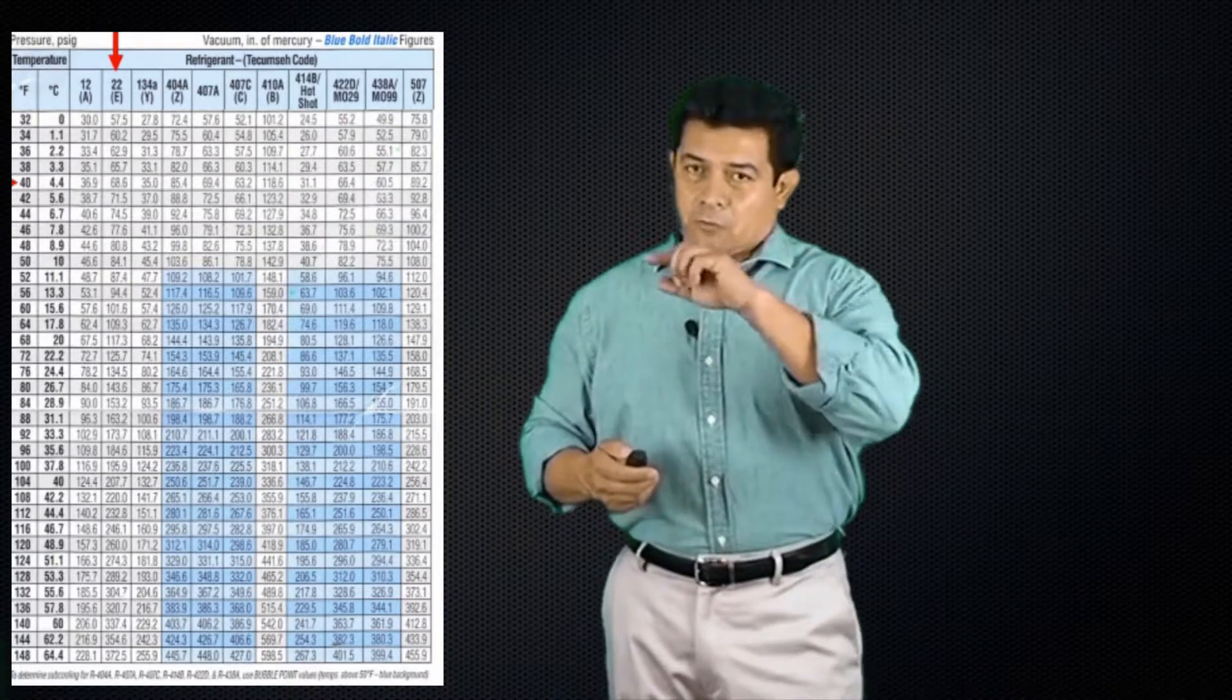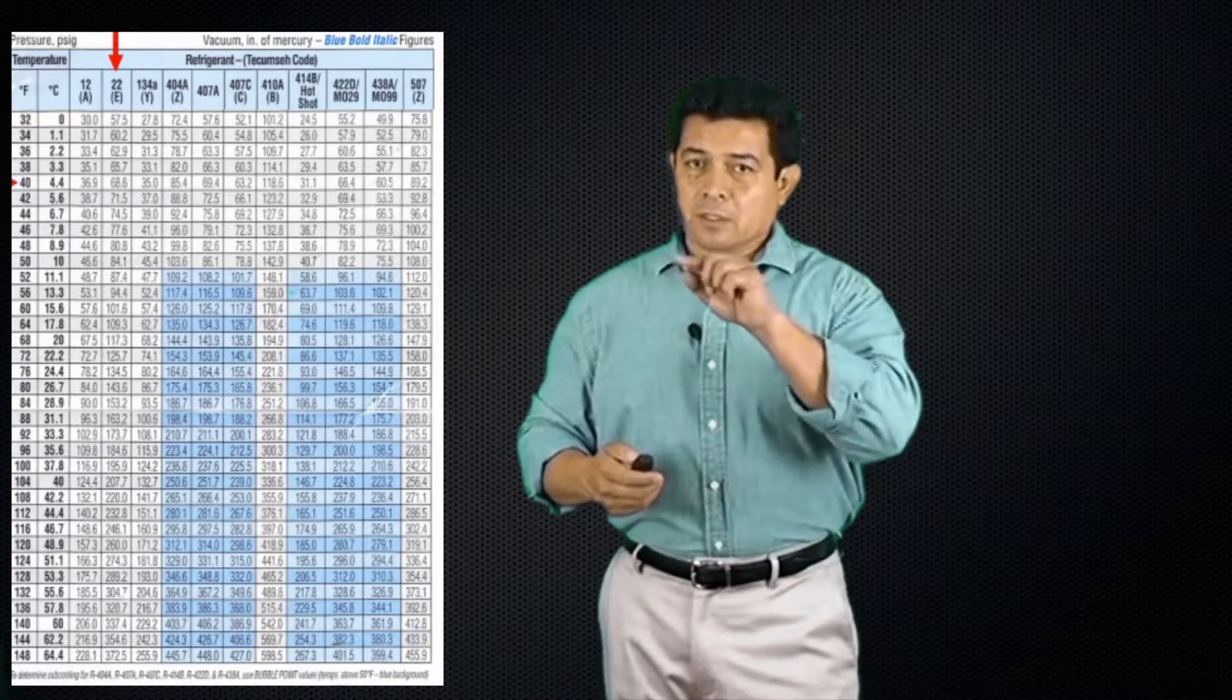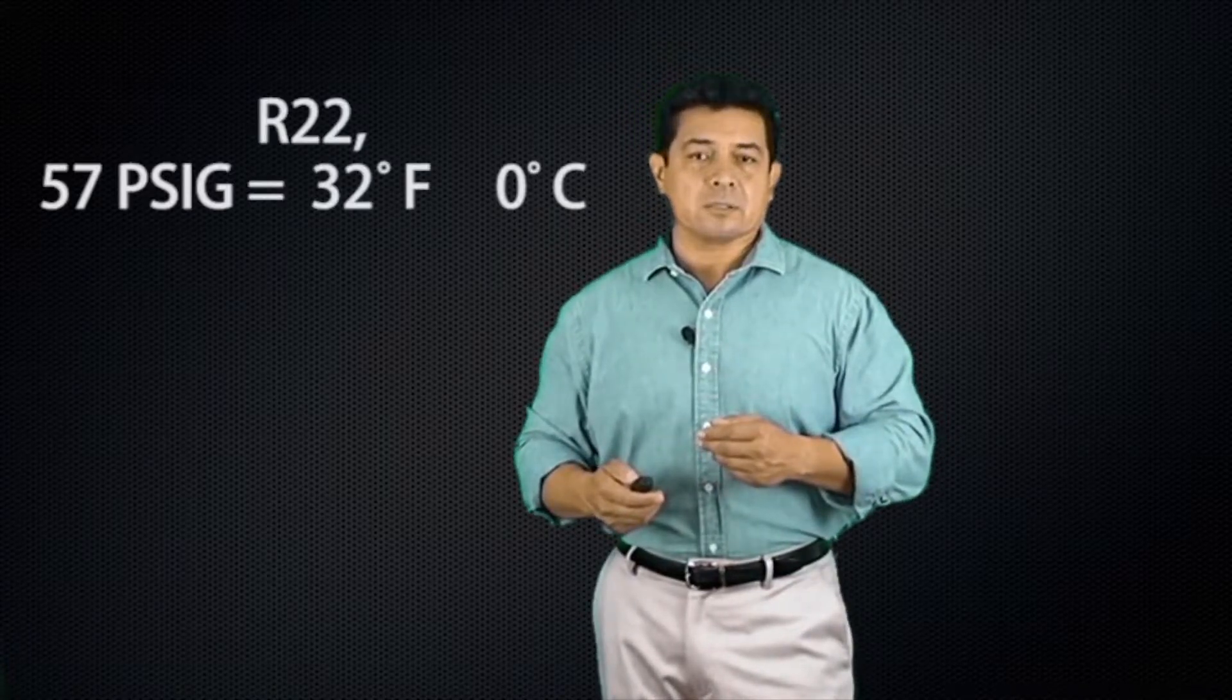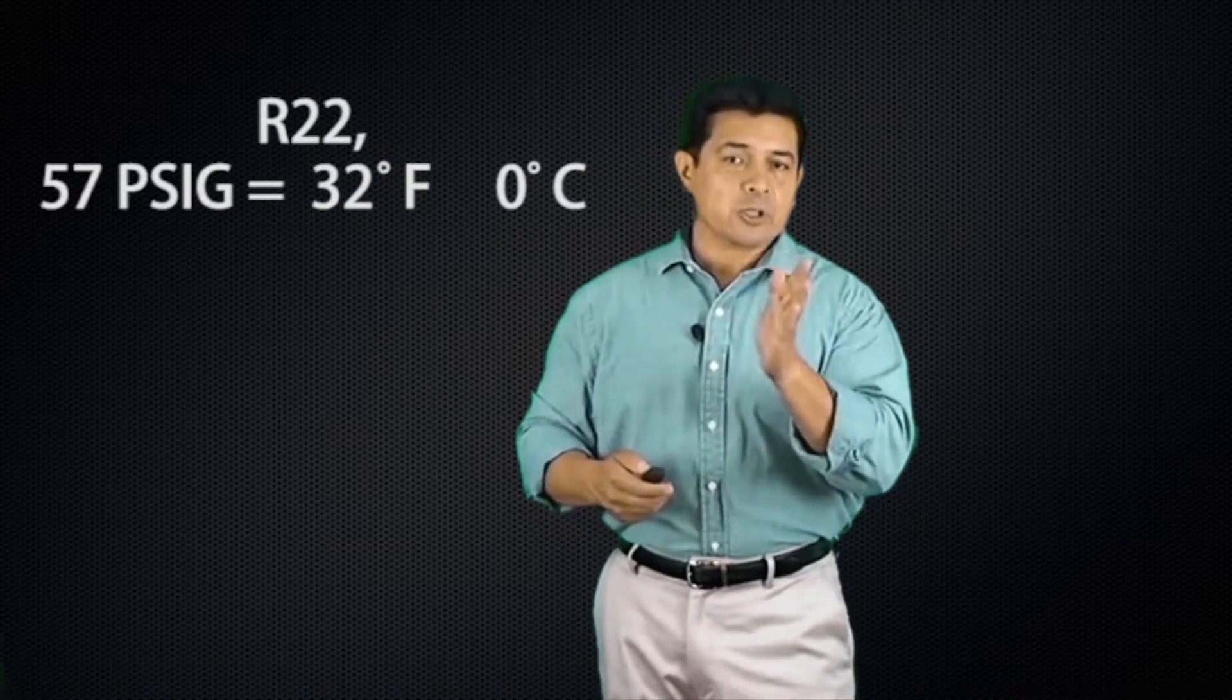Now, if you think about 32 degrees Fahrenheit or zero degrees Celsius, what happens at those temperatures? Well, water starts to freeze. So, if we were to look at a PT chart and we look at 32 degrees and check to see what the pressure of that refrigerant is at 32 degrees, if we're dealing with R22, then that pressure is going to be 57 PSIG. So when I see that the pressure drops down to 57, that tells me that my coil is at freezing point. It's going to freeze. It's going to ice up, which of course is not good.